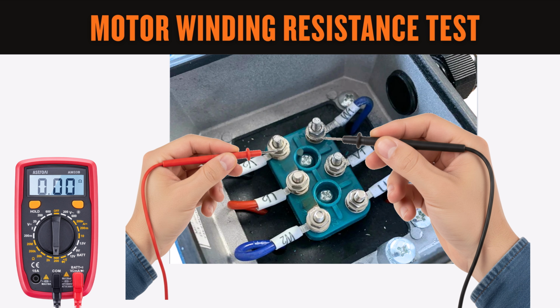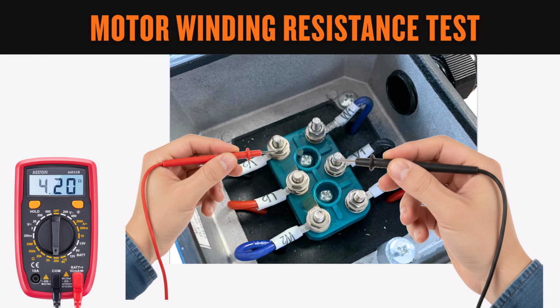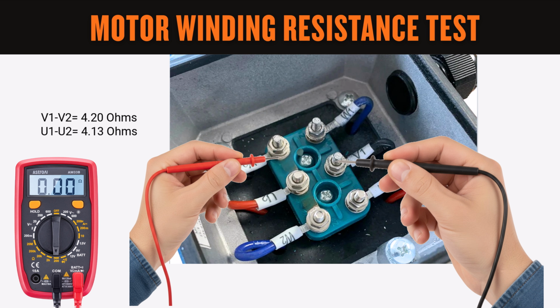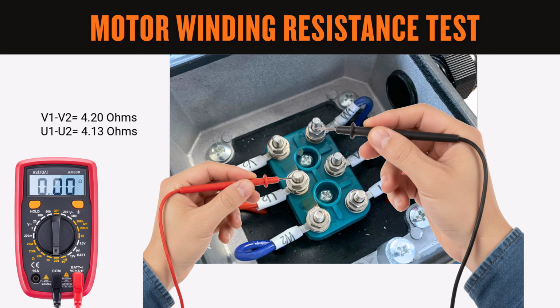I am checking between V1 and V2. Remember, forget about the number written on the terminal. It might be wrong, so we check one by one. It's a matter of hardly 1 or 2 minutes, very quick and simple. Once I get the proper V1 and V2, I measure the resistance of the coil. It's showing 4.20 ohms, which means this phase is perfectly good. This winding is healthy and balanced. That's our first phase confirmed.